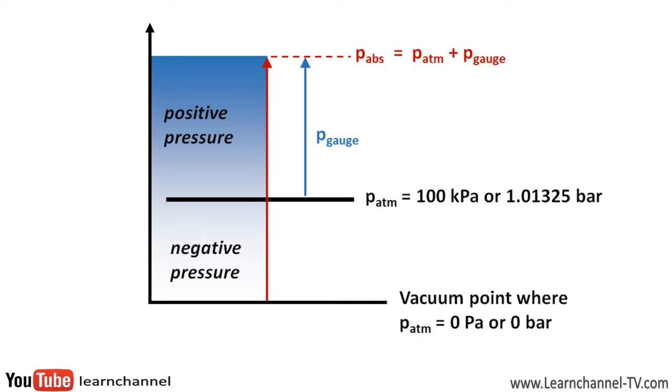This absolute pressure is referenced against a perfect vacuum. By the way, we have an absolute vacuum in space. The gauge pressure, on the other hand, is referenced against ambient air pressure. As the name suggests, it is the pressure value that you read on the pressure gauge, also called a manometer. For example, our compressor delivers a pressure of 7 bar, which is what we read out at the pressure gauge. So actually, we have an absolute pressure value of about 8 bar.